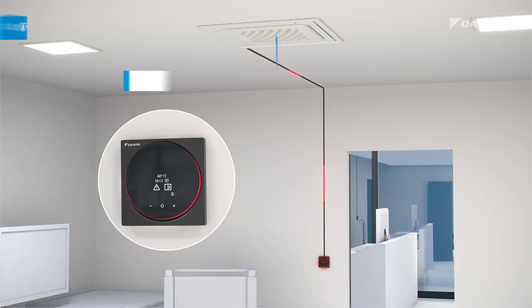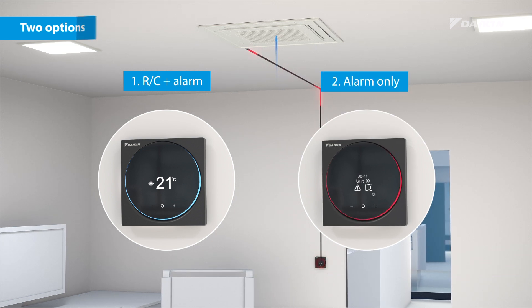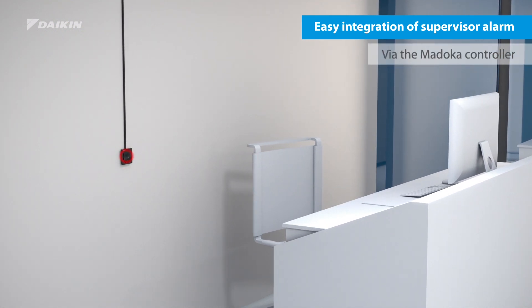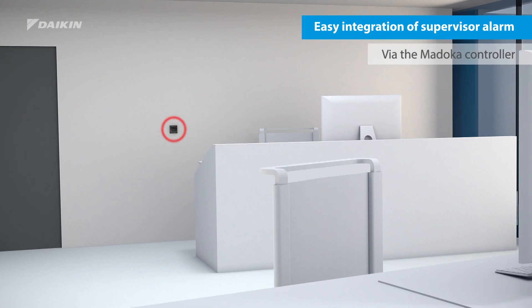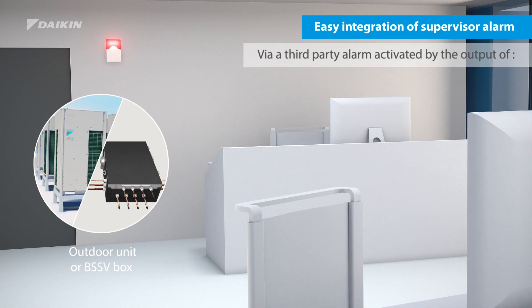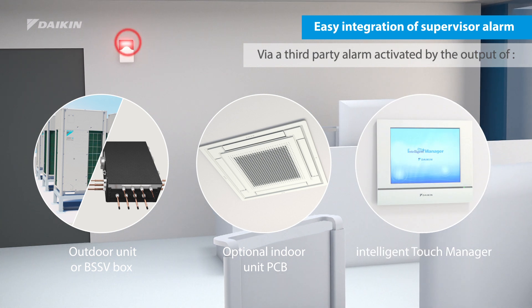By a field setting, the Madoka controller can be set to alarm only. If a supervisor alarm is required, it can easily be integrated via the Madoka controller or as a third party alarm via an output of the outdoor unit or BSSV box, via the indoor unit or through the intelligent touch manager.